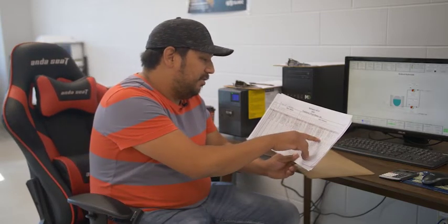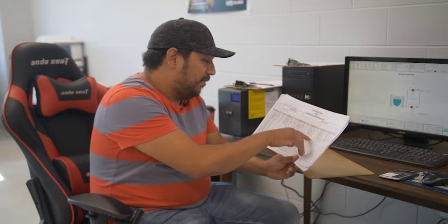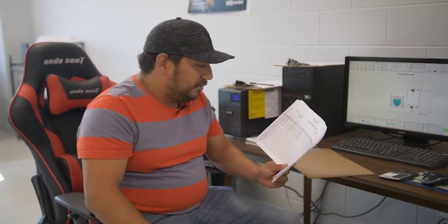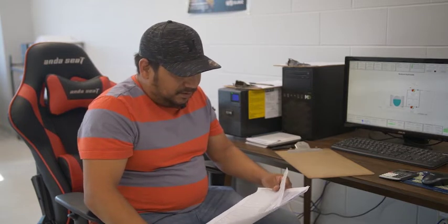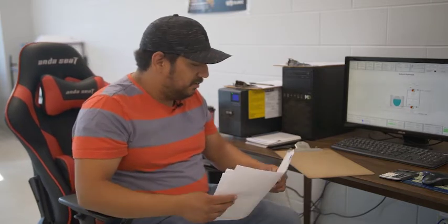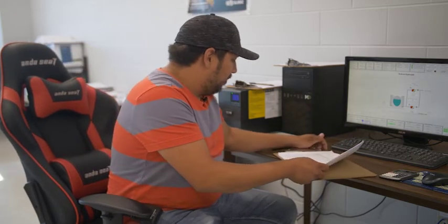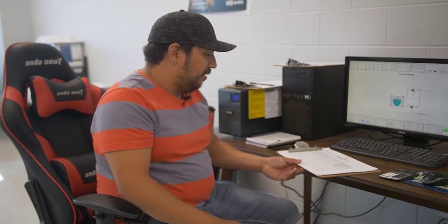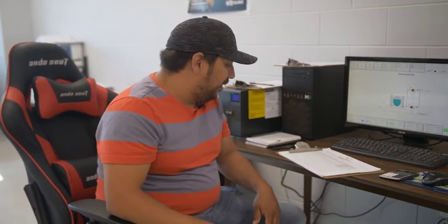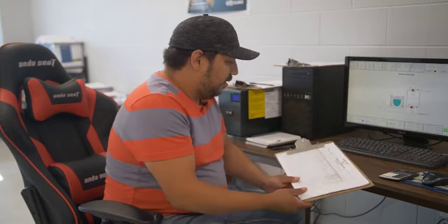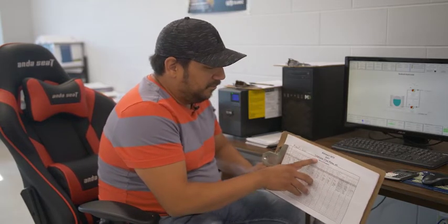Ultrafiltration units: if we notice one unit is using more than the other unit or treating more water, like last week, we saw train number 2 being used quite a bit versus train number 1. We actually had an issue with train number 1. It all stems back to our clarifier and the upset that occurred there. So we noticed that UF number 1 was backwashing a lot more because it was getting high turbidity alarms, that sort of thing. So we weren't treating as much water then. And then we decided to do a recovery clean after that occurred, and I'm probably going to do another recovery clean today.